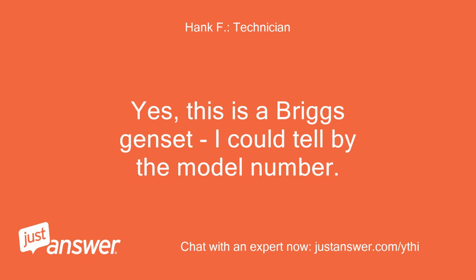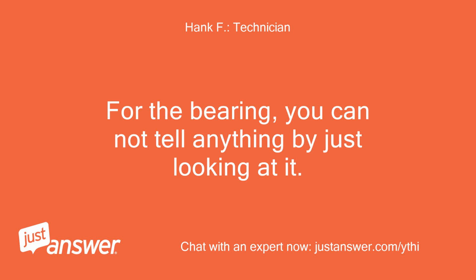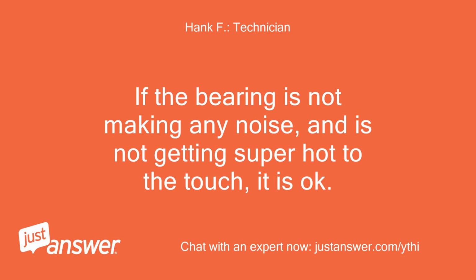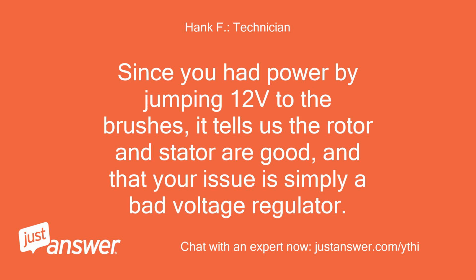Yes, this is a Briggs genset, I could tell by the model number. For the bearing, you cannot tell anything just by looking at it. If the bearing is not making any noise and is not getting super hot to the touch, it is okay. Since you had power by jumping 12 volts to the brushes, it tells us the rotor and stator are good, and that your issue is simply a bad voltage regulator.